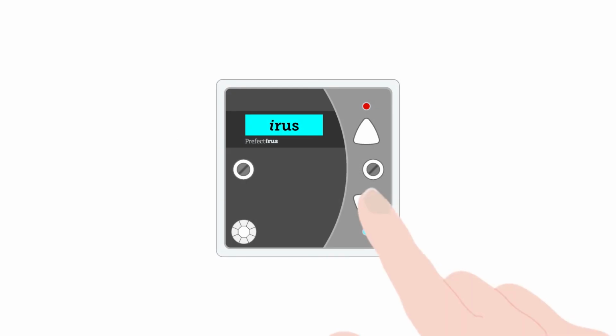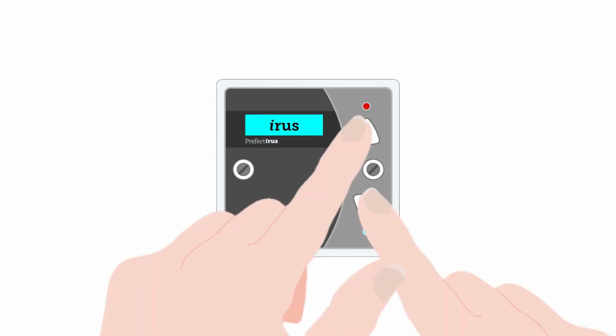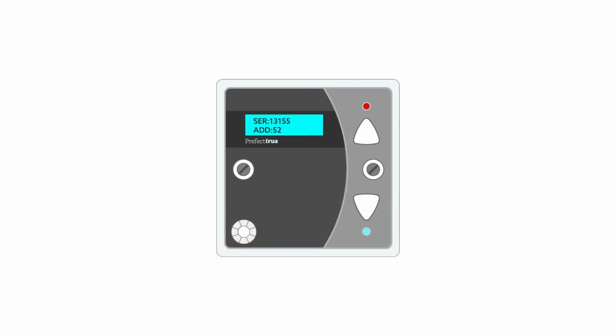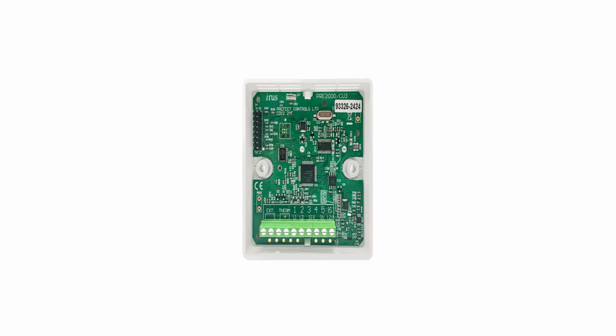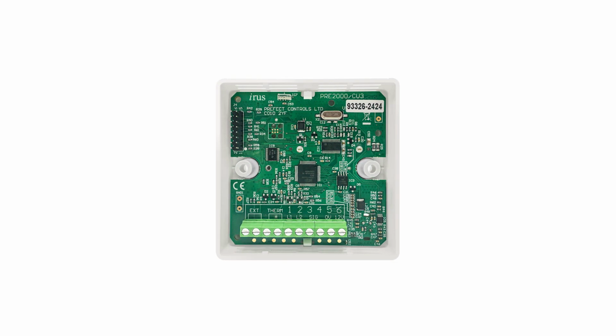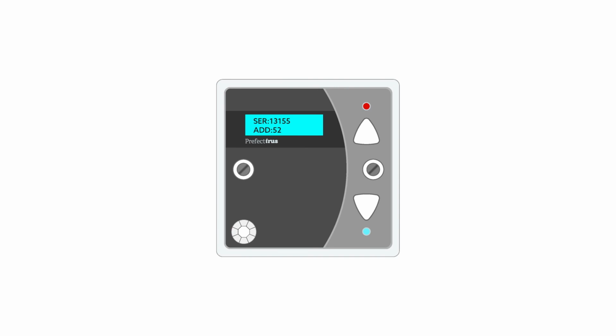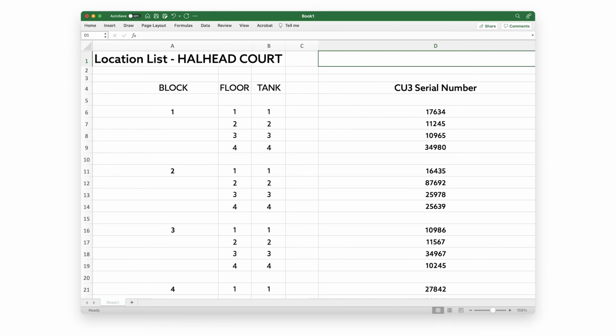Each control unit has a 5-digit serial number. To find this, press and hold the down button, and then press the up button 3 times in quick succession. The serial number will appear on the screen. Do not confuse this with the manufacturing number that is printed on a label applied to the back of the unit. The number on the screen is what we need to assign to the tank, so we can begin our commissioning process. You should log the serial numbers on an Excel spreadsheet. We can provide you with a template for this if required.